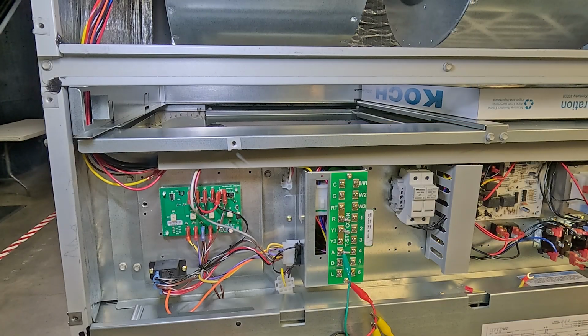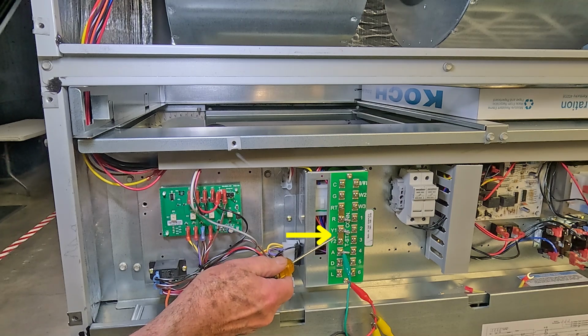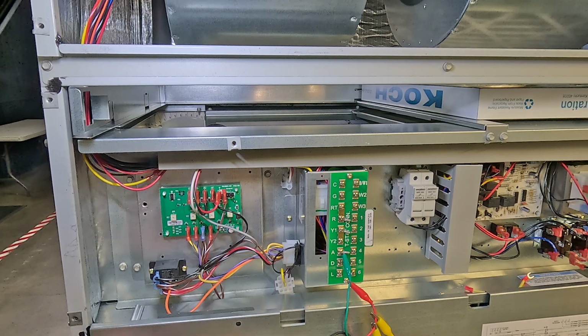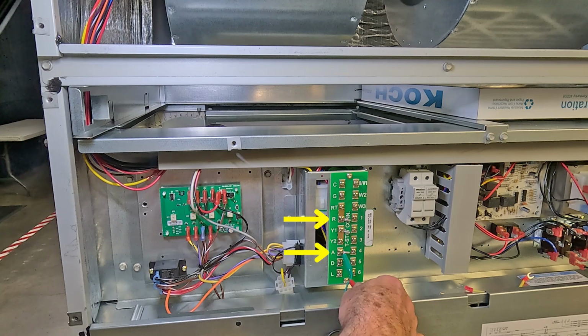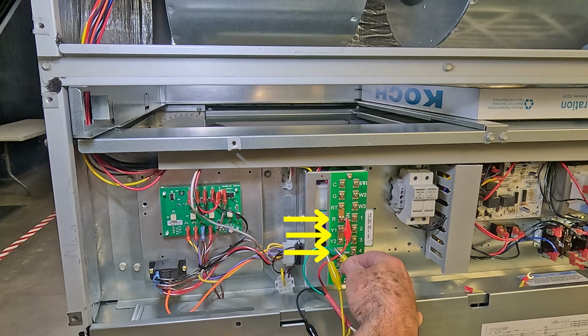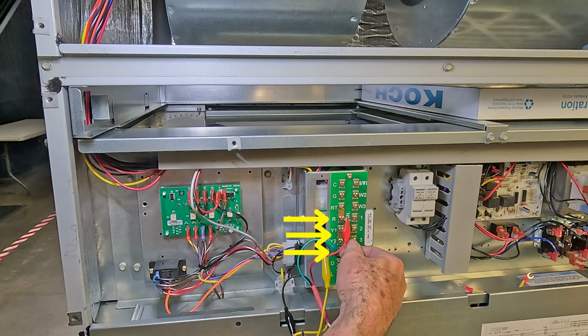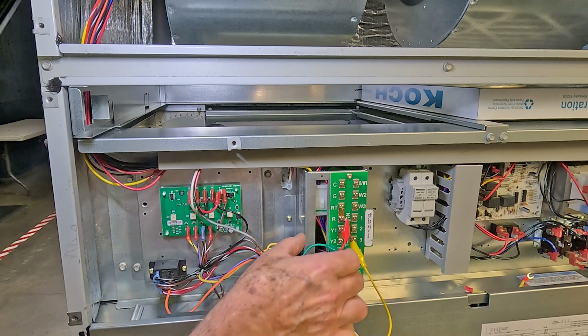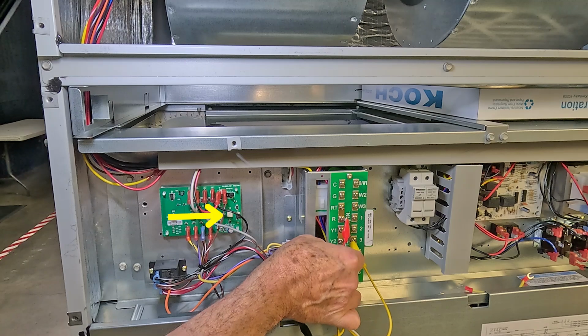For a basic non-CO2 sensor single-stage compressor unit, set the occupied OCC and pre-purge PP pots the same as 2-stage compressor unit as previously discussed. On this single-stage compressor unit, there should be a brass jumper installed between Y1 and Y2 on the bar terminal block. Jumper R to A and either Y1 or Y2 because the brass jumper is installed, and set the Y2 pot switch to your desired damper setting.